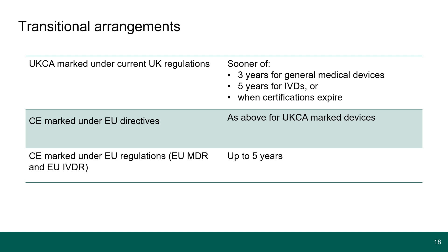So moving on to the transitional arrangements. For UKCA marked devices under the current UK medical device regulations, these products will be subject to a 3-year transition period for general medical devices and up to 5 years for IVD products. The same timelines apply to devices CE marked under the EU directives. For devices CE marked under the EU MDR and IVDR, these will be subject to a 5-year transition period. For clarity, CE marked devices can continue to be placed onto the Great Britain market after the 30th of June 2023.